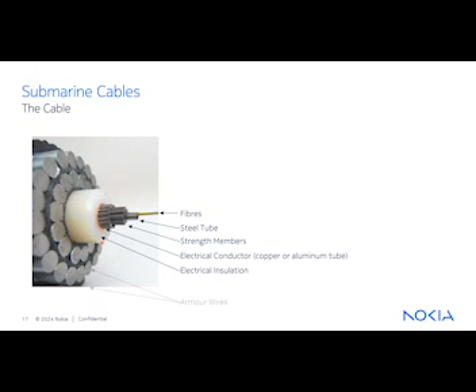Once you have this core that the whole submarine cable system is built upon, you'll put different layers of armor. If there's one layer like this inner one, it's called single armored. In this case it's two layers, so we call this double armored cable. Again, the electrical insulation, the armored wires. You have this basic core, and we wrap things around it to strengthen it, but the basic core runs through all the types of cable.